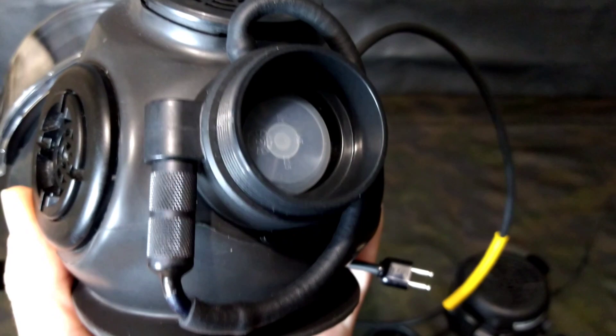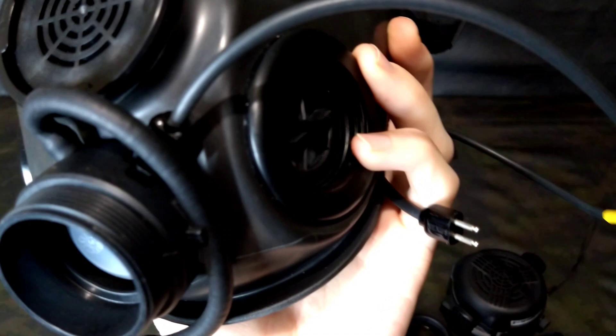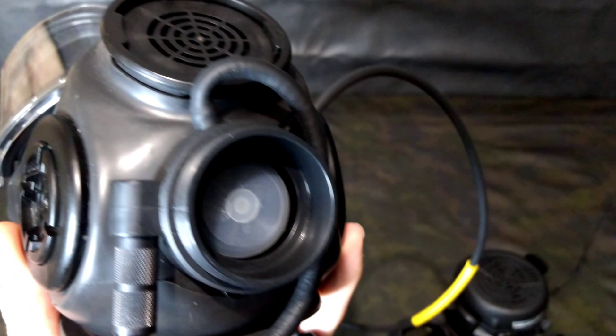As you can see, the drinking tube wraps around this housing and fits into a small clip molded onto the side. There are simple cutouts for the drinking tube and the communications port. I can go ahead and remove this entire housing from the exhalation valve, because these adapters are only held onto the outlet valve body with red urethane adhesive — a red plastic adhesive, almost like super glue.